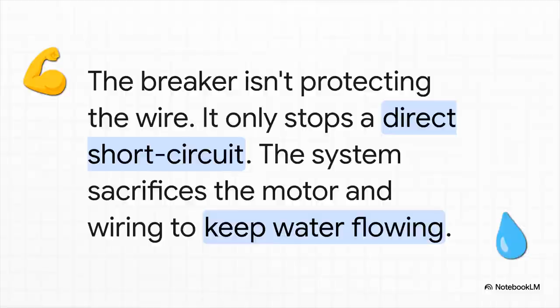So why? Why go through all this trouble to create such a brutal, sacrificial system? Well, because when you step back from the circuit diagrams and the codebook, you realize this isn't about wires and motors at all. It's about people. And this is the whole philosophy right here. Run to failure isn't some kind of flaw. It's the entire point. The pump, the controller, the wires, they are all disposable. Because in a fire, the only thing you can't get more of is time. Time for firefighters to do their job, and time for people inside to get out. This system is engineered to buy that time, whatever the cost.